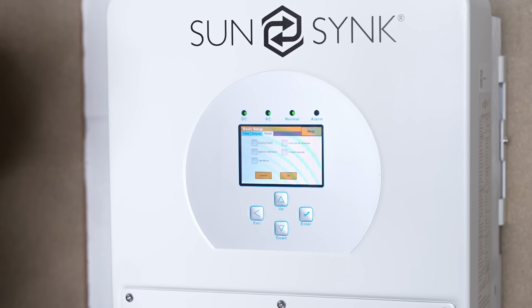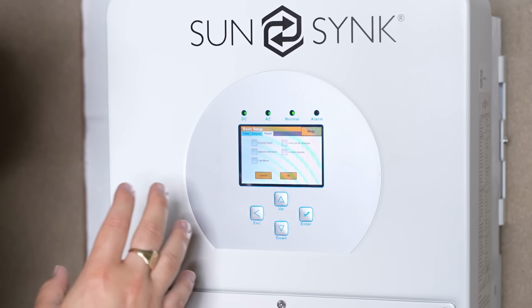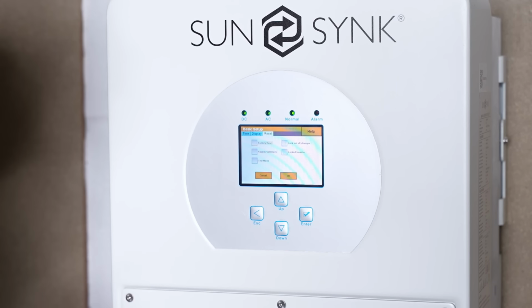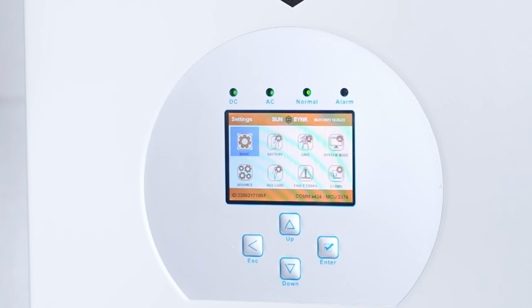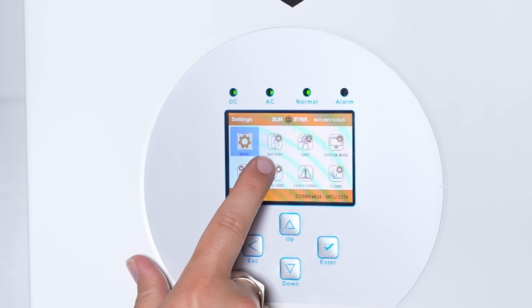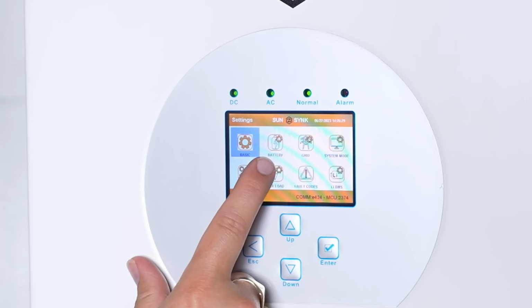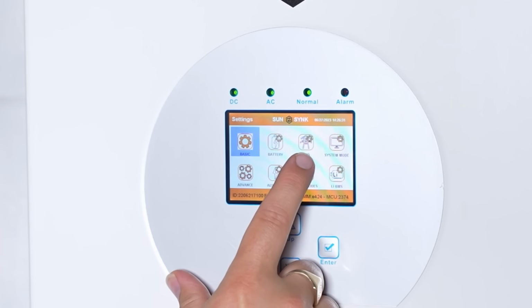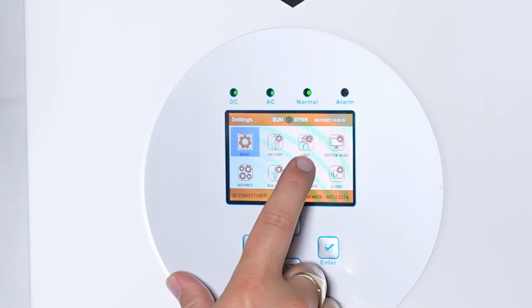Reset includes options to lock out all settings and to run a self-test on the inverter. That's normally required for other countries such as Italy. The battery section sets the parameters for your battery. This is set at commissioning and should not be altered. The grid setting should not be altered on the inverter. It should be set to G98/G99.